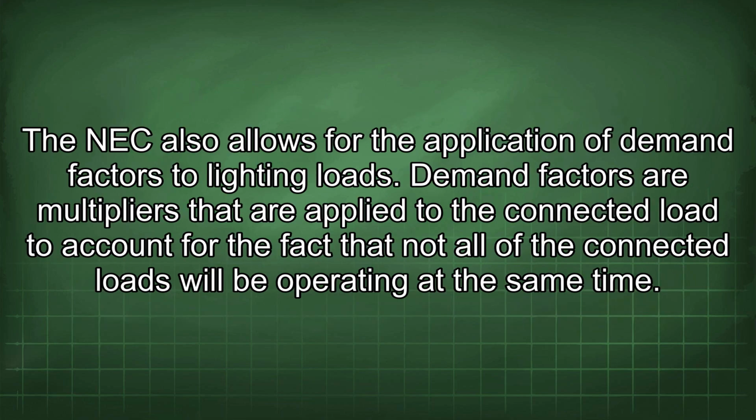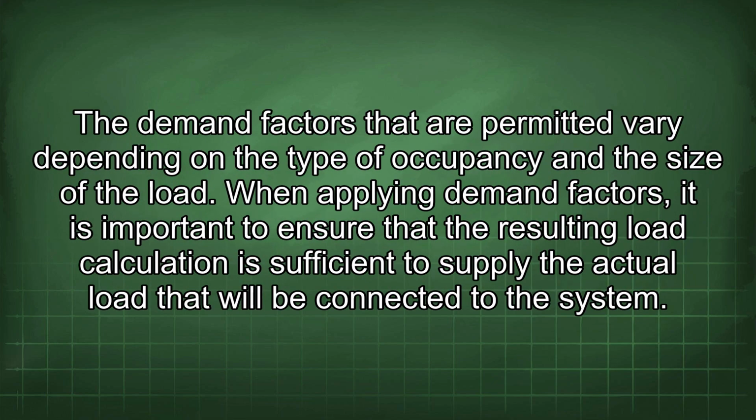The NEC also allows for the application of demand factors to lighting loads. Demand factors are multipliers that are applied to the connected load to account for the fact that not all of the connected loads will be operating at the same time. The demand factors that are permitted vary depending on the type of occupancy and the size of the load. When applying demand factors, it is important to ensure that the resulting load calculation is sufficient to supply the actual load that will be connected to the system.